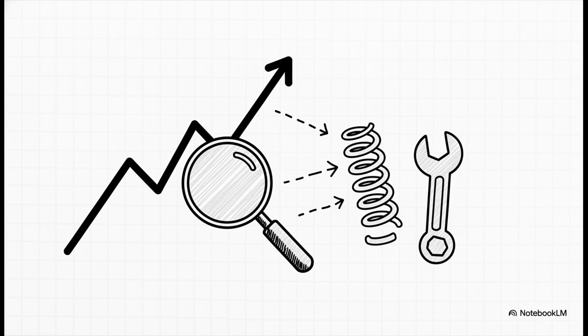And the most important takeaway from this whole section: track the gradual drift. Do not just wait for a hard alarm to go off. If your spring charging time slowly creeps up 15% over a 6-month period, that is a glaring maintenance signal. It's worth investigating immediately, well before it hits that hard failure limit.